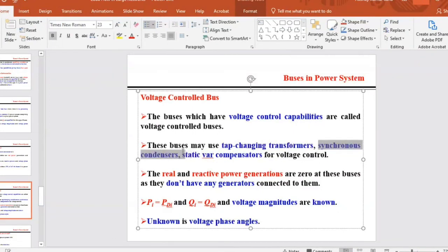We use synchronous condensers, which are synchronous machines like generators, but they only supply reactive power, not active power. Since they supply only reactive power, we call them synchronous condensers—we run synchronous generators or machines to supply only reactive power to the system.